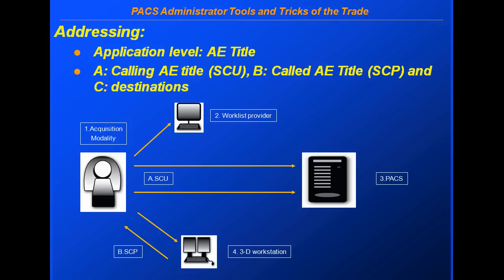The second class of AE titles is the Called AE title. That is the AE title used when another device wants to communicate or open an association to the particular device where you want to configure the DICOM settings.